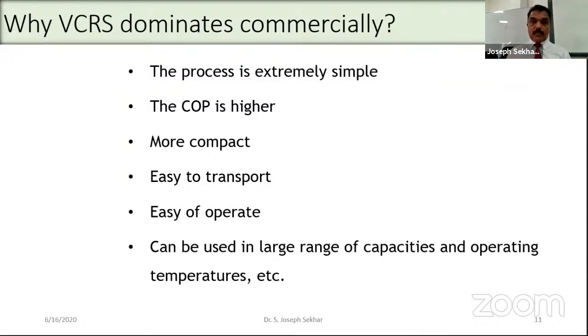You know what COP is? It is the ratio between the amount of energy given to the refrigeration system to pump a particular quantity of heat from low temperature to high temperature. So a good COP means with less energy given to the system, we can pump more quantity of heat.